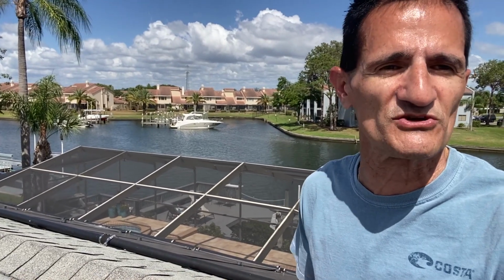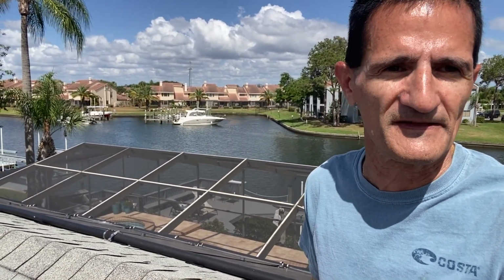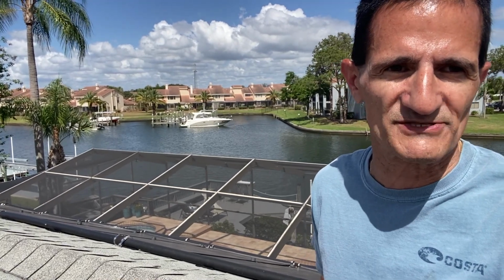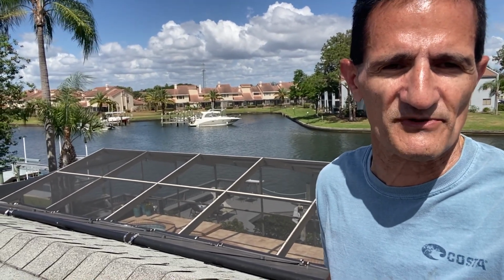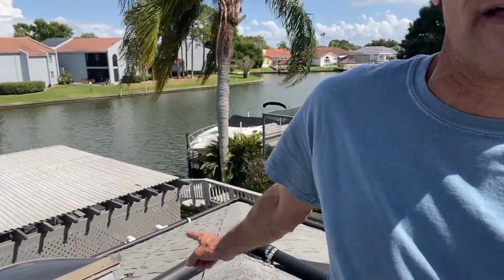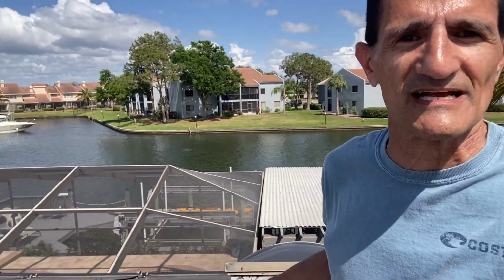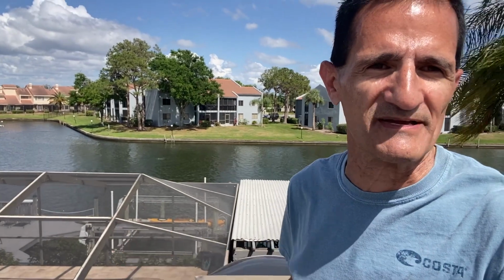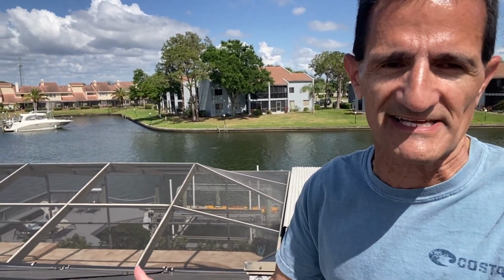So for instance, a 2-story, a tile roof, those cost more money to install, and also what sort of supplies and materials we need to replace. So sometimes the pipes get warped up. Now these are actually in very good shape, but sometimes being out in the heat, they get very warped. Sometimes we need some solar panel fittings, or sometimes even in some cases have to replace the solar panels if they're too old and they're too brittle, because these are made out of plastic.